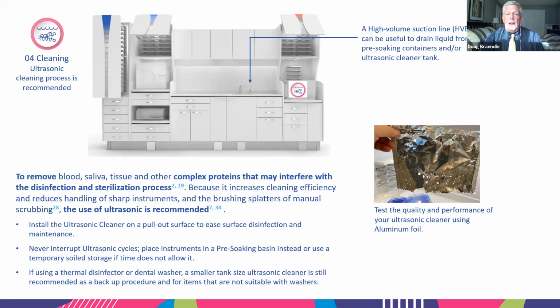And should you have a transducer that's not working, what you will find is you'll have holes and dimpling on one side, and the other side will be perfectly smooth. That's screaming at you that you have a transducer that's broken. So it's time to call the dental dealer and see if we can get that fixed, because if you're using double-ended instruments, those instruments on that side are really not getting clean. They're just jiggling around in dirty water.